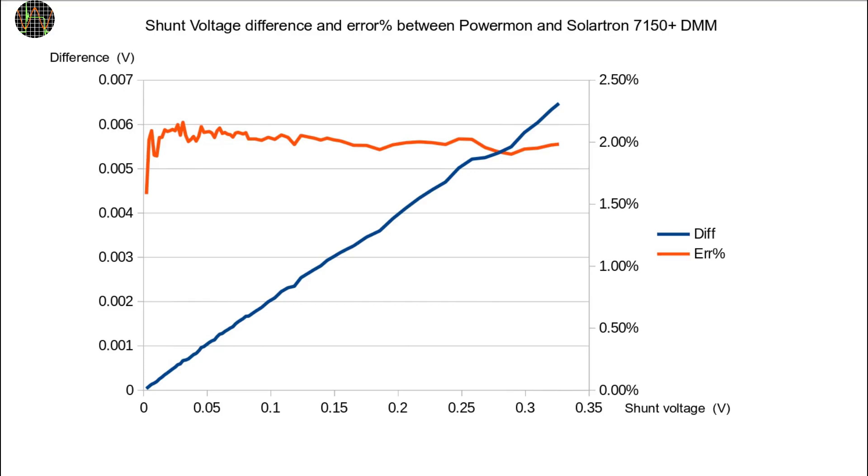This graph shows the result. The red error line is almost horizontal at about 2%. This means the error is large enough that it should be compensated but also that it can be easily fixed using the same slope and intercept method I explained in the previous Powermon video.